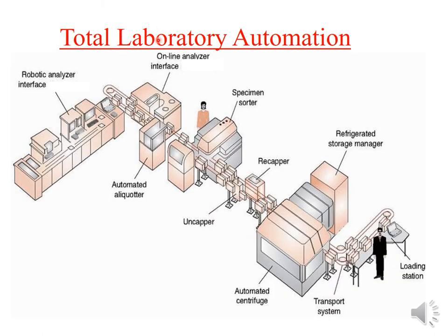This total laboratory automation encompasses all phases of analysis, all automated. It starts from loading of the sample, transport of the sample, centrifugation, refrigeration and storage, and capping and uncapping of the sample, then specimen sorting.